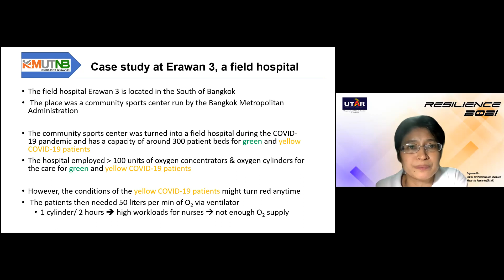In this case, the patients then need 50 liters per minute of oxygen via ventilator. A standard oxygen cylinder contains 6 cubic meters of oxygen, so it will be gone in 2 hours. That leads to high workloads for nurses to change the cylinders, and also there was not enough oxygen supply. So we were contacted by the hospital staff at the Erawan 3 Hospital, and the research team spent about a week setting up an oxygen generator.